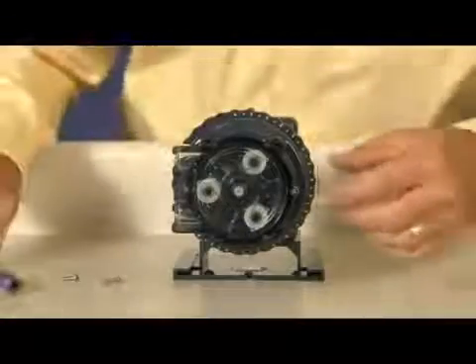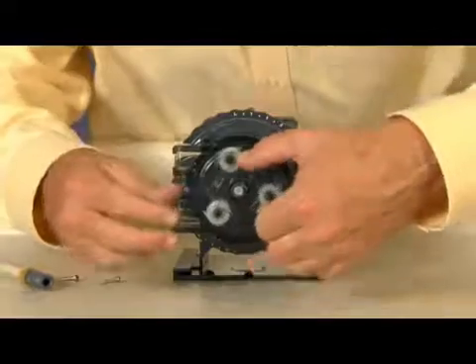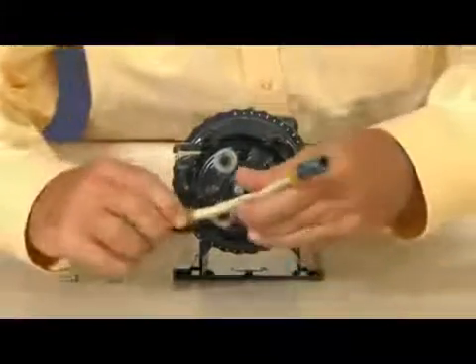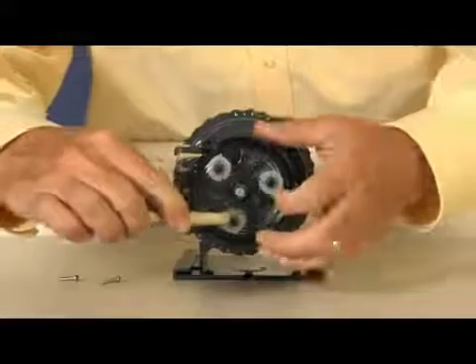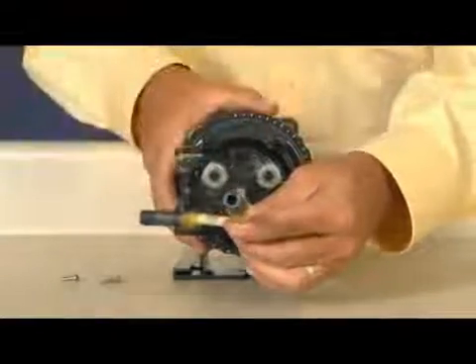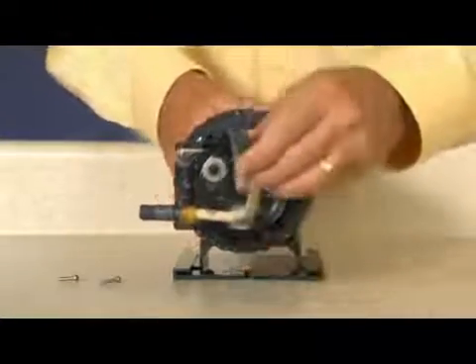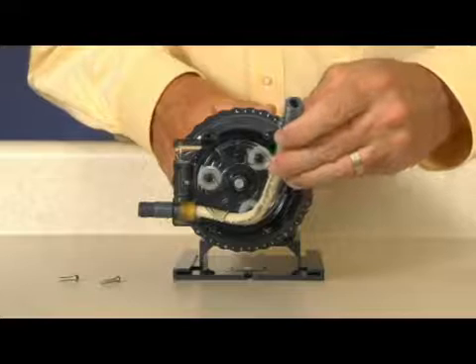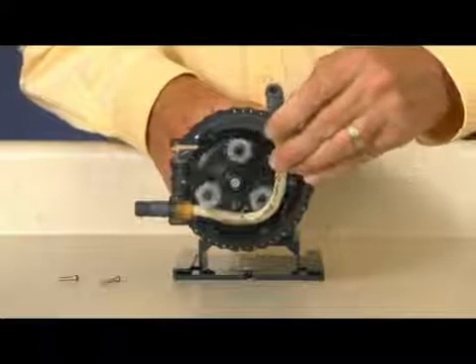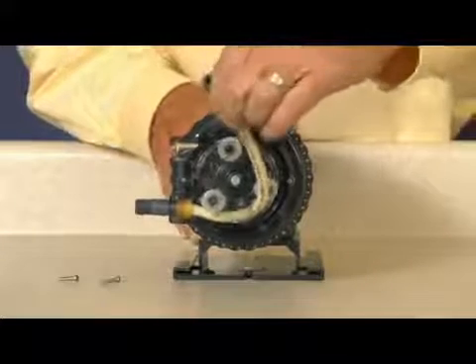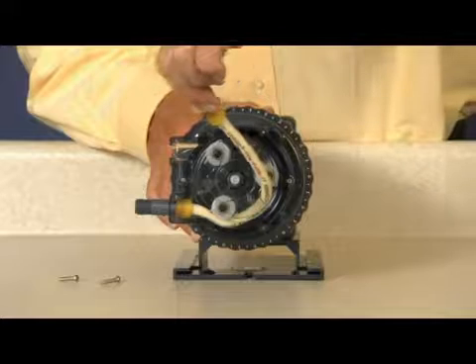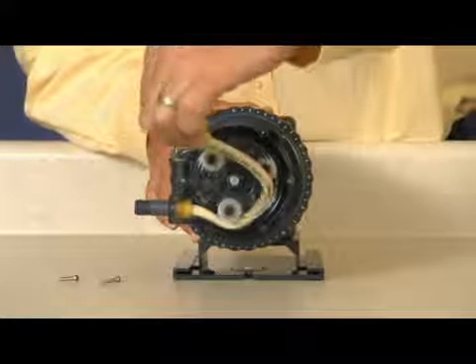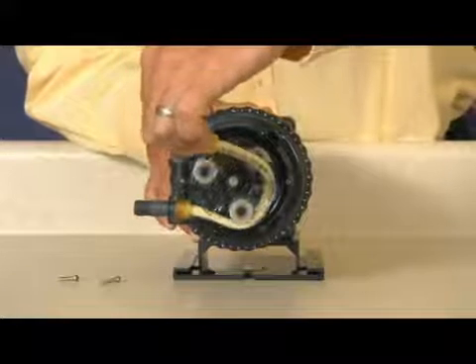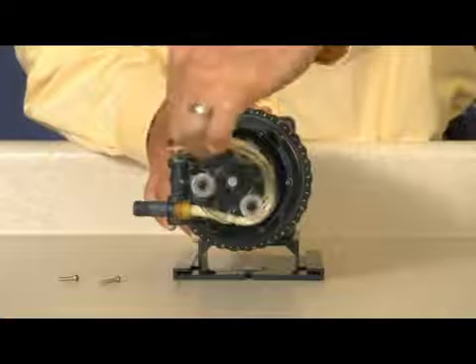To install the pump tube, manually rotate the roller assembly counterclockwise to align one of 3 roller assembly slots with the suction side housing slot. Place the tube fitting into the suction side slot of the housing and the roller assembly slot. With the pump setting on L or 1, hold the tube fitting and jog the roller assembly by turning the pump on. It is important to avoid rotating your wrist, which can result in a twisted tube that will not center. Do not force the tube, and be careful of your fingers.